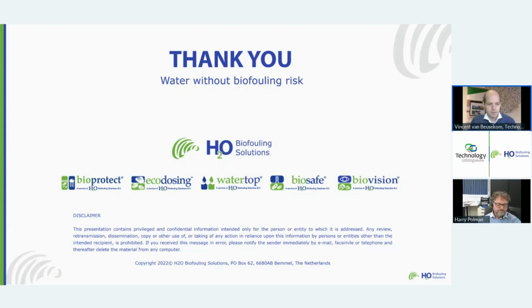There are actually two questions related to that. Does it also mean there's a requirement for filtration of the mussels to protect critical downstream components? No, because in freshwater systems we allow them to grow, depending on the location and what the client accepts. In the Netherlands, at these locations, we let the mussels grow to a couple of millimeters, so when they die they can still flush through the condenser without blocking it, keeping the system clean.